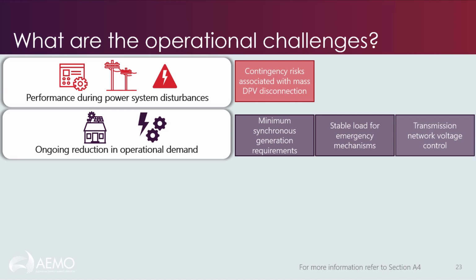At the transmission level, high levels of DPV operation can displace the operation of utility-scale generation, which may be providing reactive power services. Additionally, high DPV generation reduces the loading of transmission lines, and as a consequence, network voltages increase, which can eventually exhaust network voltage management measures, such as transformer tap changing and reactive plant switching.